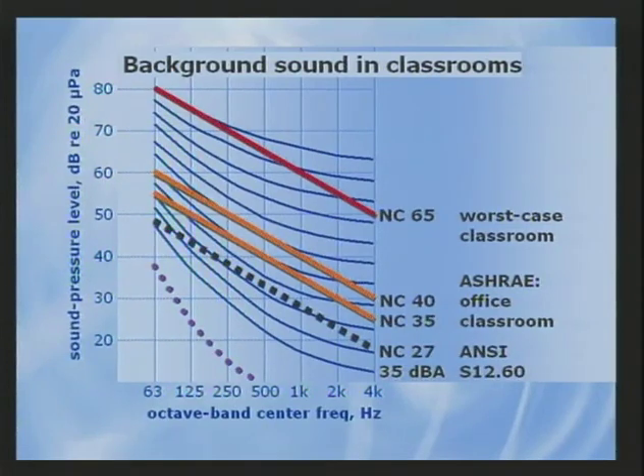Notice that the 35 dBA requirement is approximately equal to NC27. Two things are evident from this figure. Although the Ohio study did find schools that meet ANSI's requirements, it revealed that unrestricted classroom sound levels can be much too high to provide good speech communication. The chart also shows that ANSI's recommendation is significantly lower than the commonly used design targets for background sound.